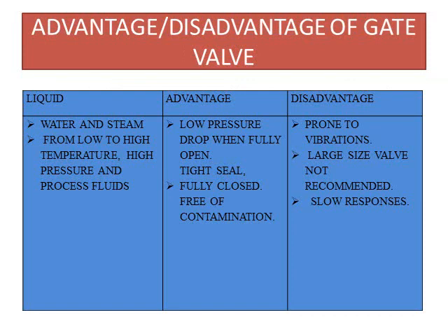Here you can see the advantages and disadvantages of the gate valve. The gate valves are basically used for water, steam from low to high temperature, high pressure and process fluids. The advantage of the gate valve is a very low pressure drop across the disc during fully open condition and tight seal condition. These valves are fully closed and free of contamination.